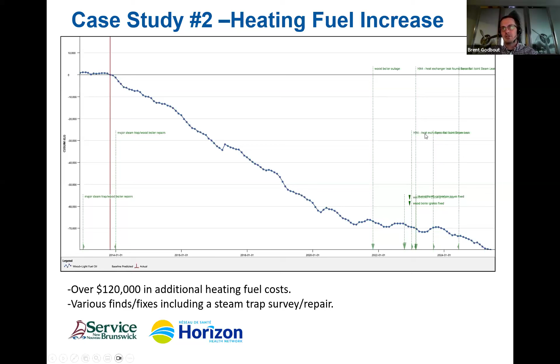Ultimately, we did do a whole lot of work. This shows you all the things we were trying to do to fix this problem and couldn't figure it out. We had several boiler outages where we went in and fixed some things with the wood boiler that we thought might have been adding to our energy use, and they didn't seem to fix it. Did another steam trap survey, fixed a whole bunch of steam traps. It was a heat exchanger that we fixed.